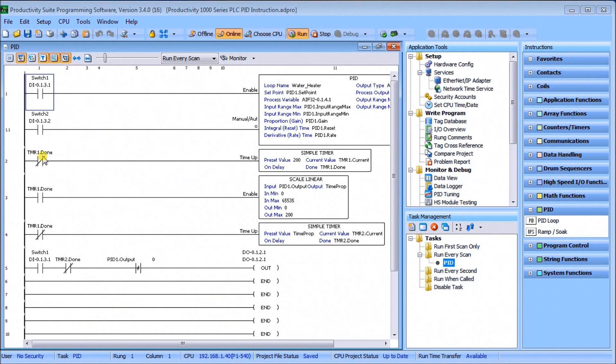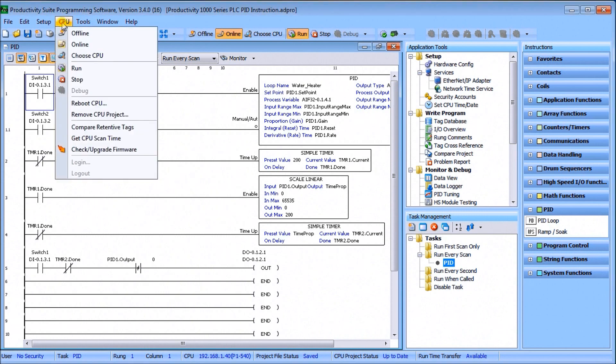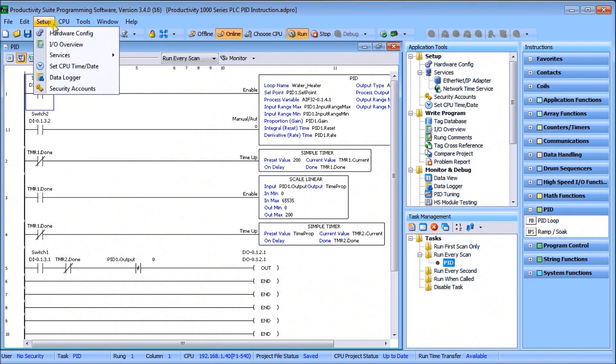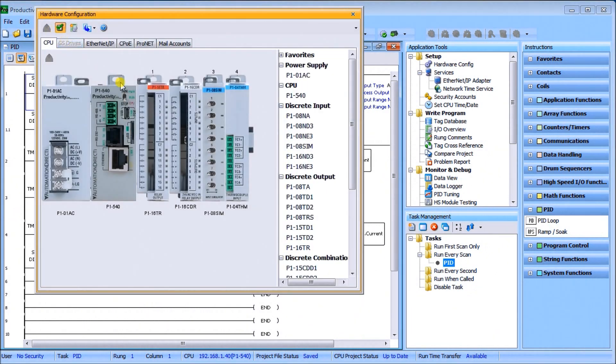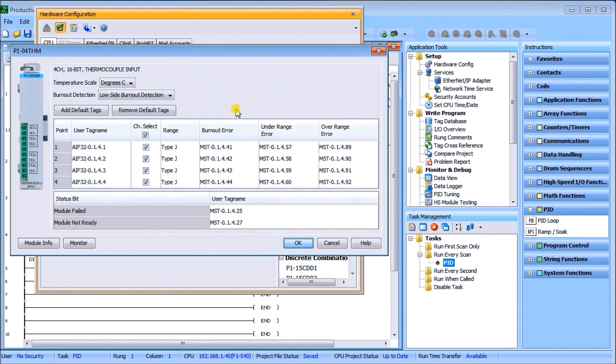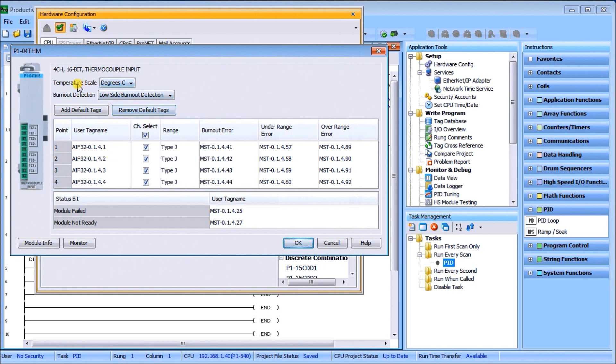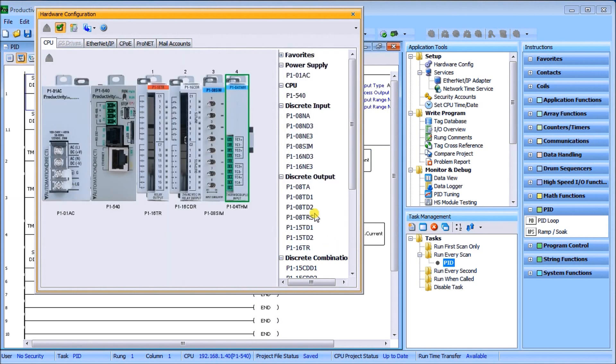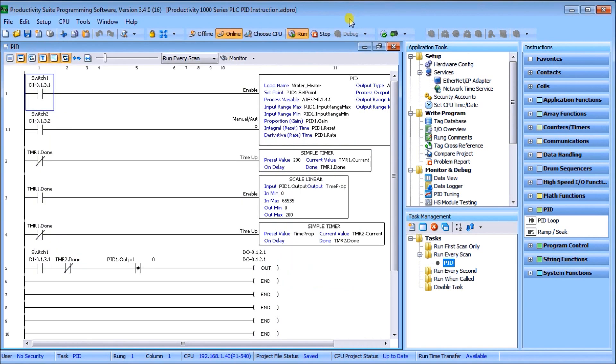Up on my screen here, the first thing we'll do is we're going to be controlling a cup of water with an immersion heater. So if we look at our CPU setup, we look at the hardware and you see we have included a thermocouple input card that has four points to it. Once we get a look at the hardware configuration, we can double-click on the actual card itself and you can see here we'll be using input point number one. There's my user tag, it automatically defaults to that, and we're going to be using temperature degree C.